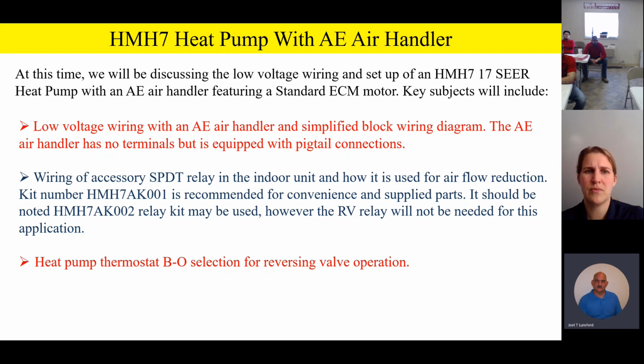This is the only heat pump in our champion lineup that utilizes the B terminal to energize the reversing valve in the heating mode. Let me say that one more time. All of our other heat pumps utilize the O terminal to energize the reversing valve in the cooling mode. So your normal champion heat pumps, your commercial heat pumps, and so on. But this product utilizes the B terminal to energize the reversing valve in the heating mode. So it's not bad, it's just different.